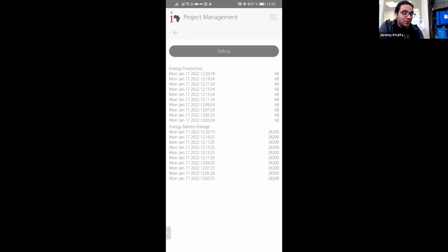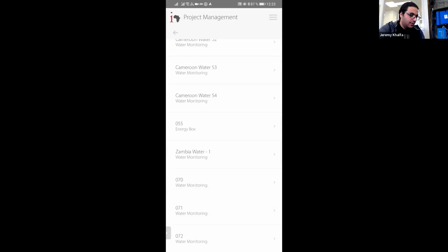So it's great. It's for you to test it, but please don't leave the site before Meir or I tell you, okay, I'm also seeing the result. By default, once we finish the installation, we change the unit to send data every hour. So once you are on site, you maybe want to change the transmission rate to every 2 minutes to check live. I changed something. Is it working? You don't want to wait the next hour to see if it's working. That's why it's important that we are involved, because only we can change the transmission rate. I can stop sharing.